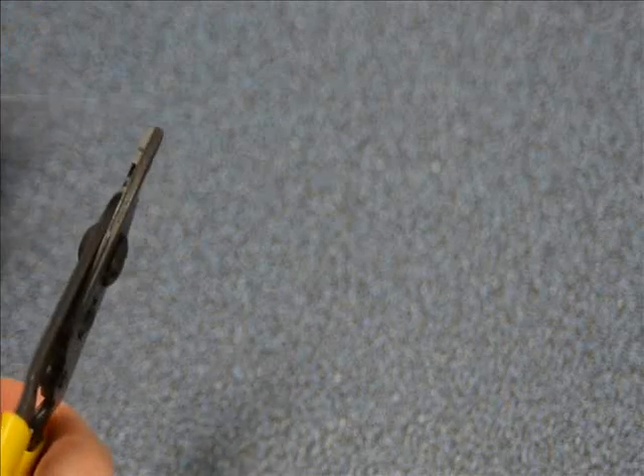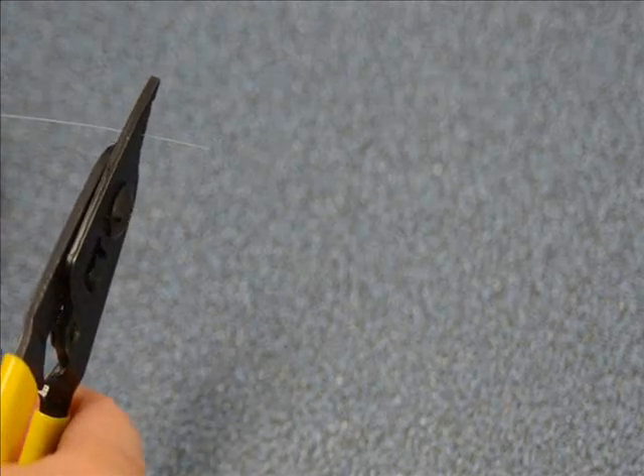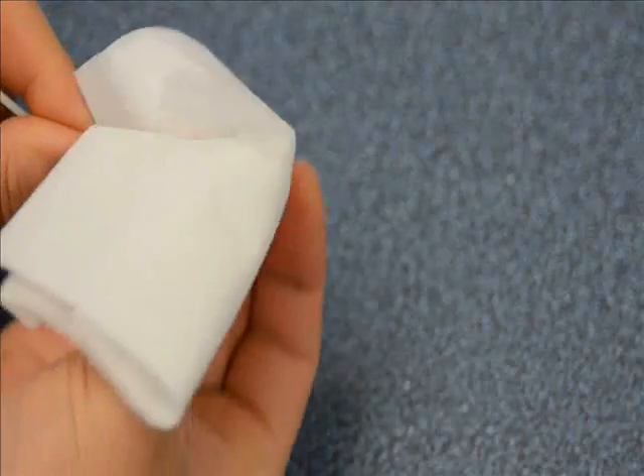The first thing we do is take the unterminated fiber and strip off approximately one inch or about two centimeters of the buffer. You moisten some paper and wipe off the fiber, and we're ready to put it in.